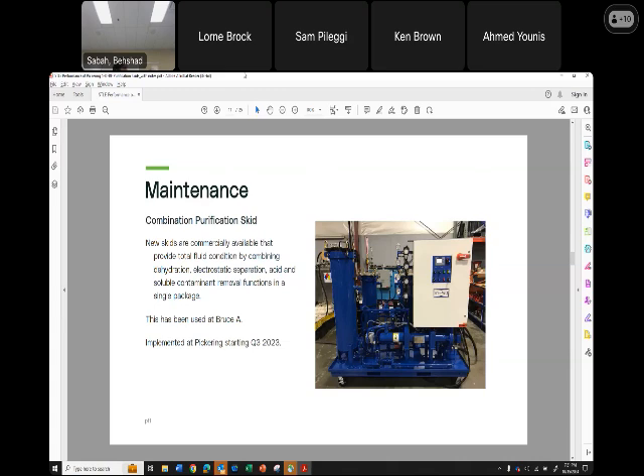We tried IX resin by itself. It was never too successful at it. We had some luck controlling acid, but we saw resistivity just drop off a cliff when we started applying it. We tried electrostatic, but we didn't control the water, so electrostatic was kind of useless because the charge plates in the electrostatic separator were not able to maintain the high voltage.